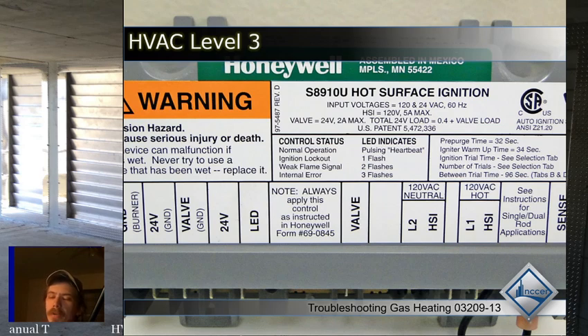Now, I will tell you this changes from manufacturer to manufacturer. They'll give you different numbers. I've seen 3 degrees, which is ridiculous. I've seen 5 degrees, I've seen 8 degrees, and I've seen 13, which is why I use 13, because 13 is a good guaranteed number.